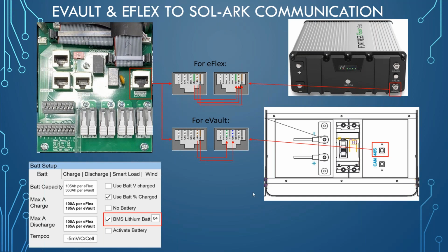With that being said though, for your battery settings, specifically for battery communications, you would put the system in the mode called BMS Lithium battery. And then you see that little number there. The number 04 corresponds to the communication style that we use with Fortress. And there's a table of those in our manual as well.